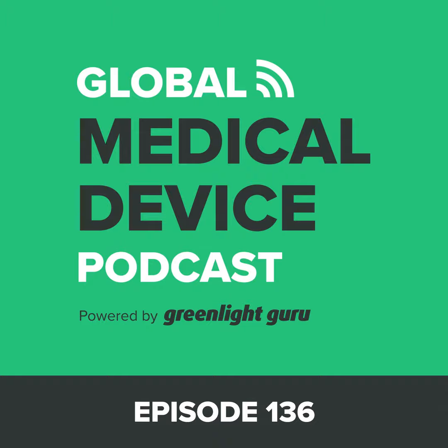Because the device needs to have software, there's a section in there on software level of concern, which is what I call software classification. Your standard information about performance testing, the usual administrative information like your truthful and accurate statement. But again, I can't emphasize this point enough, John. There's nothing new here.